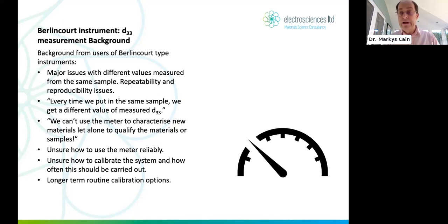So sometimes people want an absolute value, maybe traceably measured, certainly accurate. Sometimes people want to see how this has changed over time, or how my sample has changed with a slightly different composition or different electrode configuration, for example. Anyway, it all comes down to how to use this instrument reliably, how to calibrate it, how often you should calibrate it, and what about longer term calibration issues? And that's what I'll be focusing on.